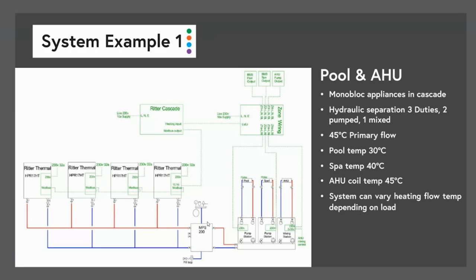buffer tank. And then on the other side, we've got pumps, and one of them's running to a pool, another one's to a spa, and another one's to an air handling unit. And what's interesting about this one is that we can run multiple temperatures on the system. So we can run the pool at one temperature, the spa at another temperature, and we can modulate the temperature of the air handling system based on heating demand through a mixing station. So it gives you lots of flexibility, and it doesn't really matter what's connected on that secondary side.